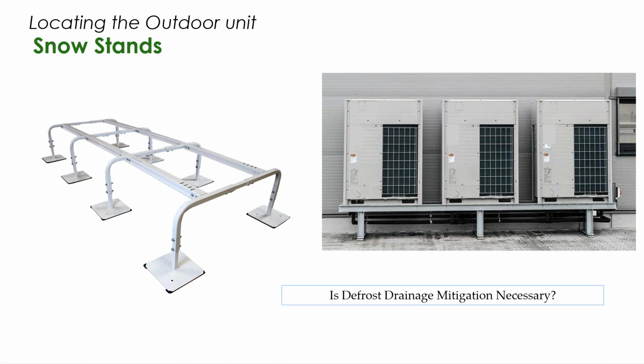From a safety standpoint, you also have to consider if you need to do any mitigation for the defrost. If the unit's placed in an area where defrost water is going to shed and ice up and cover a walkway and become a hazard for people walking, or even on a roof, is it going to freeze up and create safety issues for people working on equipment or traveling on the roof? There are various ways to handle that with temperature actuated heat trace, whether you've got to trace it to a drain so that the water can continue to drain away or drain into the soil. Those types of strategies are things you want to think about as you're placing your equipment.